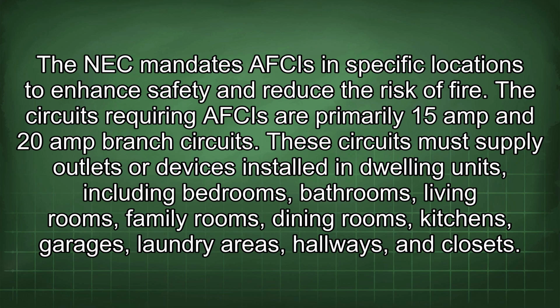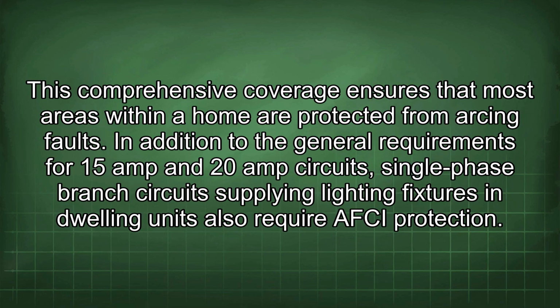The circuits requiring AFCIs are primarily 15 amp and 20 amp branch circuits. These circuits must supply outlets or devices installed in dwelling units, including bedrooms, bathrooms, living rooms, family rooms, dining rooms, kitchens, garages, laundry areas, hallways, and closets. This comprehensive coverage ensures that most areas within a home are protected from arcing faults.